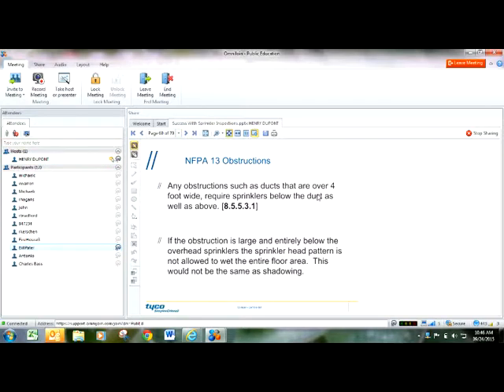If you're in an area that's an exposed type of construction open to the deck, and you have obstructions that are over 4 feet wide, say a big air duct, if it's over 48 inches and entirely below the overhead sprinkler system, you have to install sprinkler heads below that obstruction, because it's over 48 inches. You know, furniture can be below sprinkler heads too, and it can be well over 48 inches, but it's not the intention of NFPA 13 to sprinkler furniture. So it's just referring to mechanical things that are up in the air, or aesthetic ceilings, maybe a floating ceiling that is open to areas around it. If it's over 48 inches, you've got to install sprinkler heads in that as well.